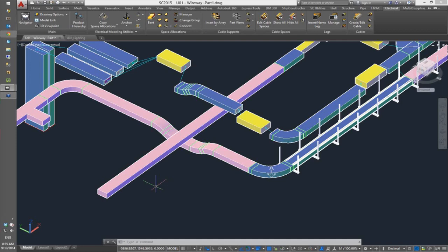And so this requires you to have certain high power, high voltage lines that will obviously interfere with sensitive lines like antennas and control cables, that type of thing. So you define your own EMC rules. The types of EMC ratings that you want to use can be as simple as power and control, or we'll take a look at one a little bit later, I think, when we get into setting up the cable routing. And we'll actually see the tree of how these are set up.